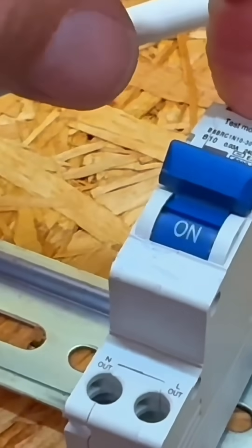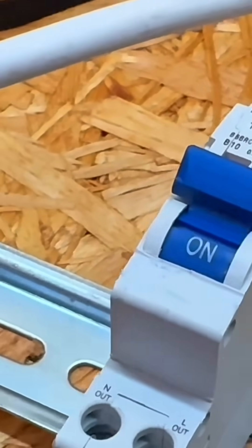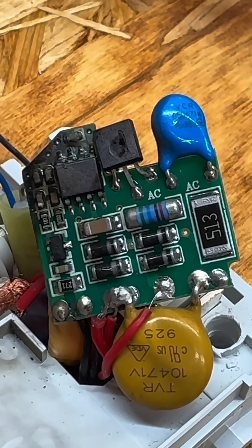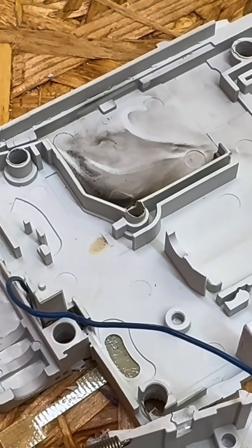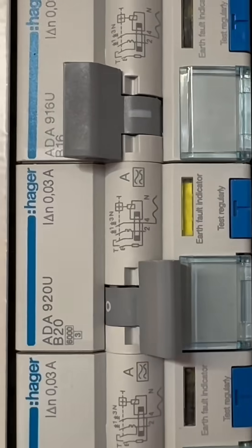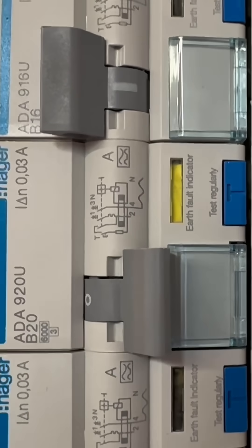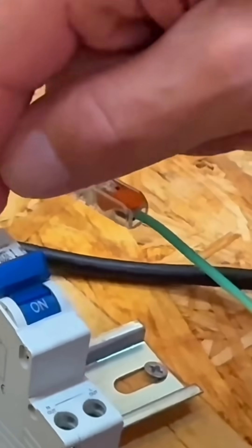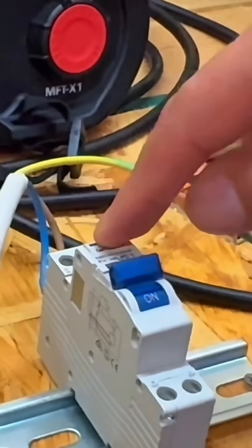So the customer's come along, the RCD has maybe tripped, they've reset it and seen everything come back on and they're happy. But is it just the test button? That smell of burning electronics. Let's try the RCD test... and obviously you've got an RCD tripped in circuit, but not this one because this one is now not functioning. The test button doesn't work, but the circuit when energized was on - we had that lamp illuminated behind us.